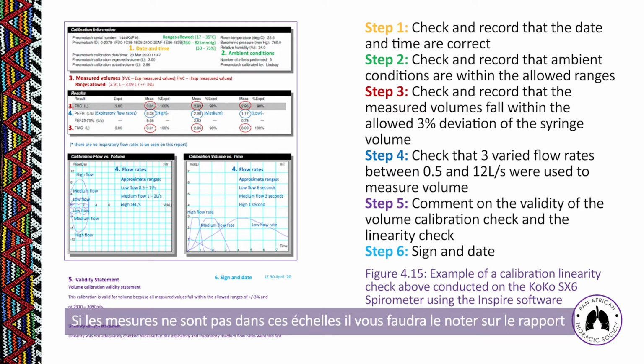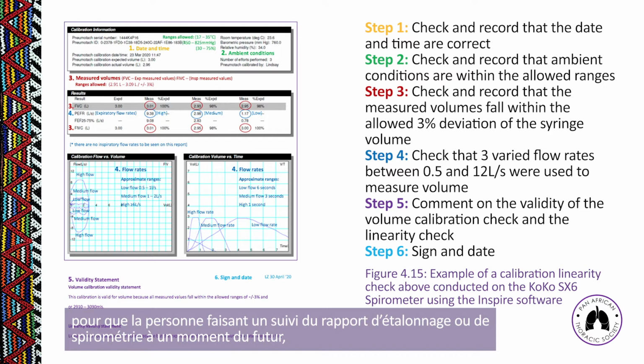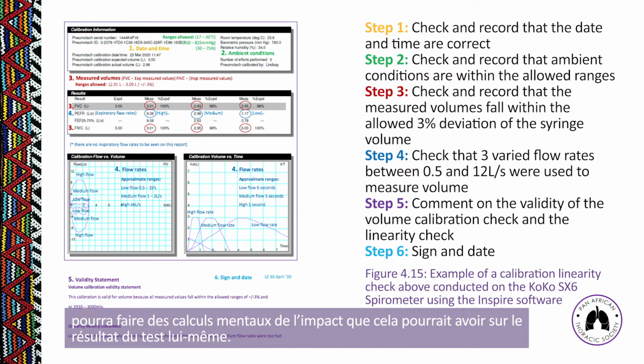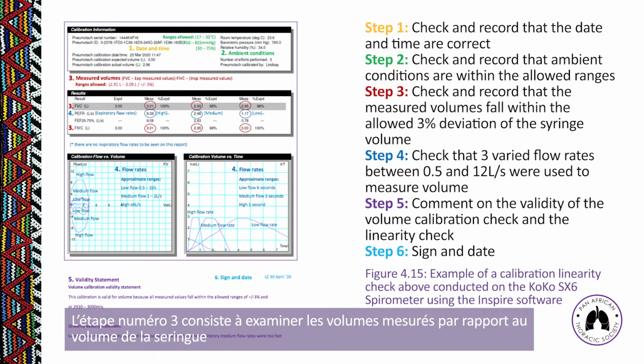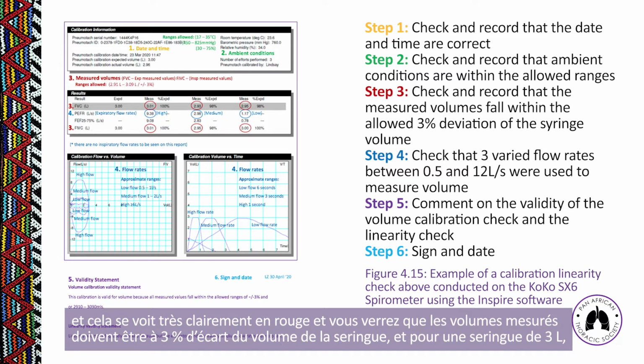If they are outside of these ranges, you would have to make a note on the report so that anyone who is then assessing the calibration report or the spirometry report at a later time would be able to make mental calculations of how that can affect the actual test result itself. Step number 3 would be looking at the measured volumes against the syringe volumes, and that is shown very clearly in the red writing.